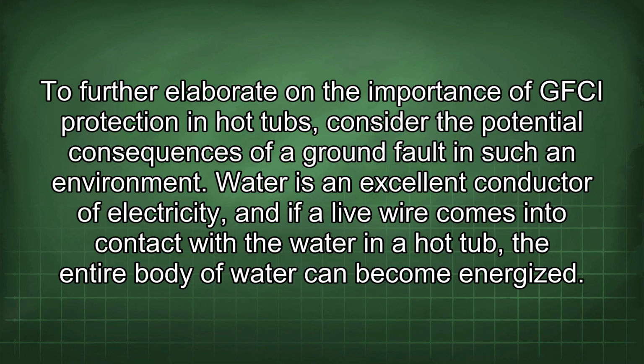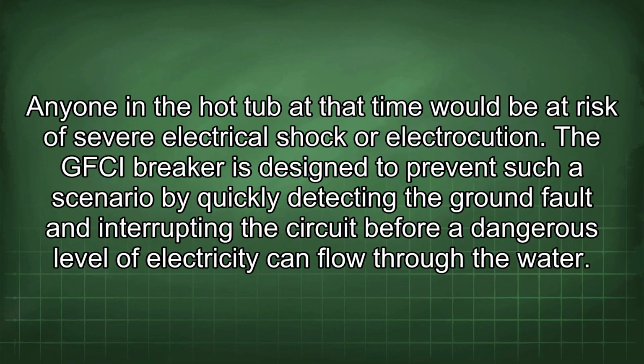To further elaborate on the importance of GFCI protection in hot tubs, consider the potential consequences of a ground fault in such an environment. Water is an excellent conductor of electricity, and if a live wire comes into contact with the water in a hot tub, the entire body of water can become energized. Anyone in a hot tub at that time would be at risk of severe electrical shock or electrocution. The GFCI breaker is designed to prevent such a scenario by quickly detecting the ground fault and interrupting the circuit before a dangerous level of electricity can flow through the water.